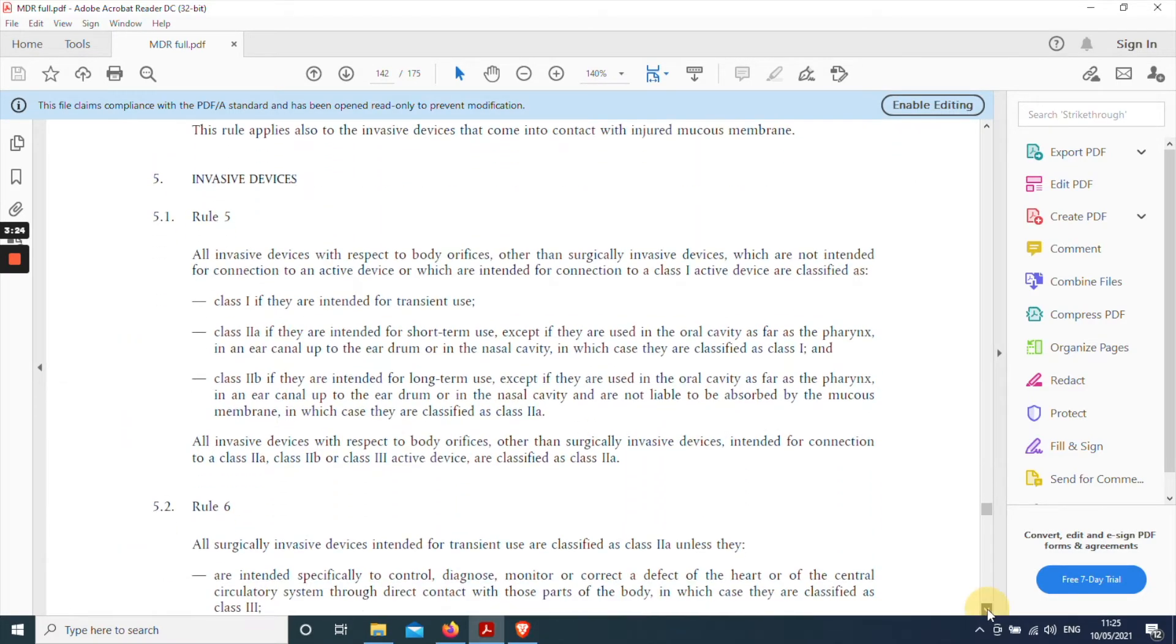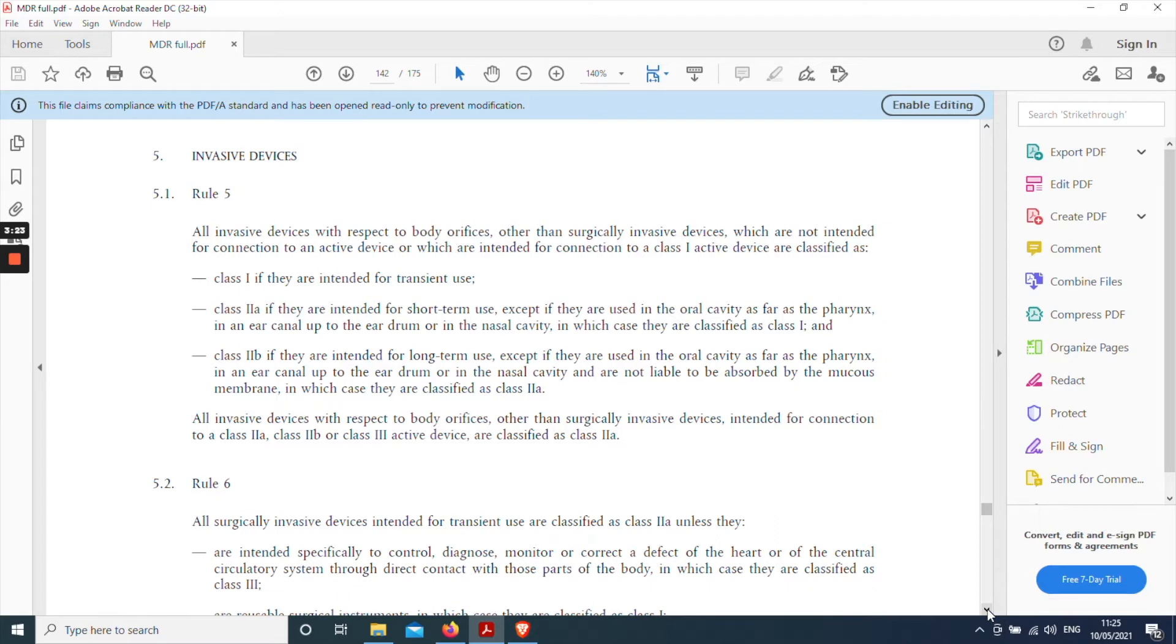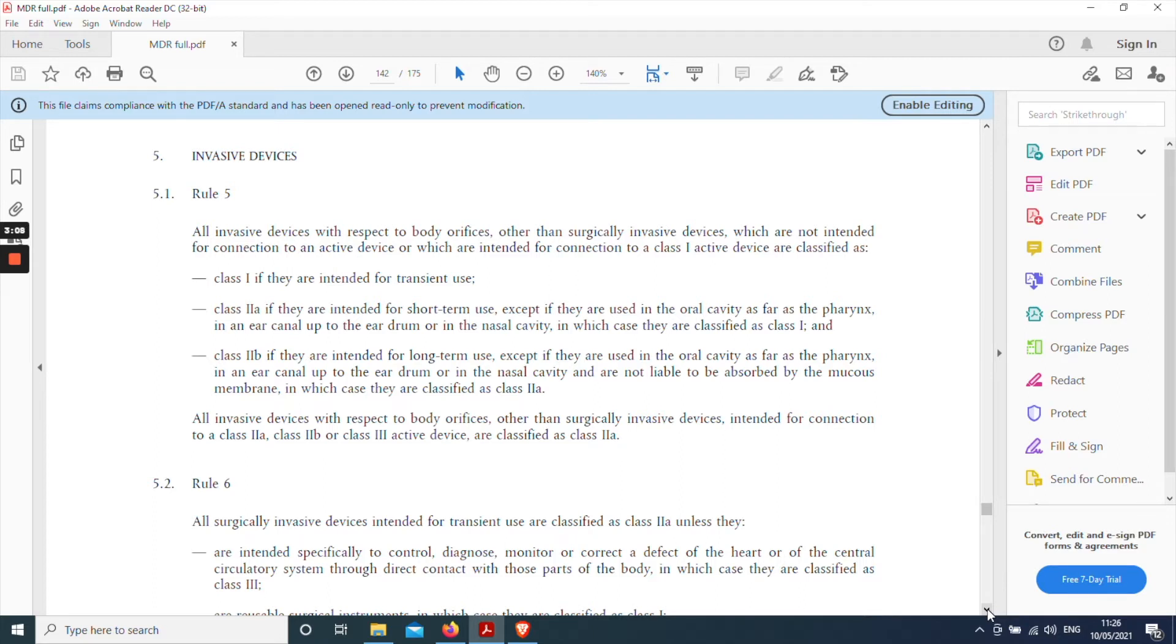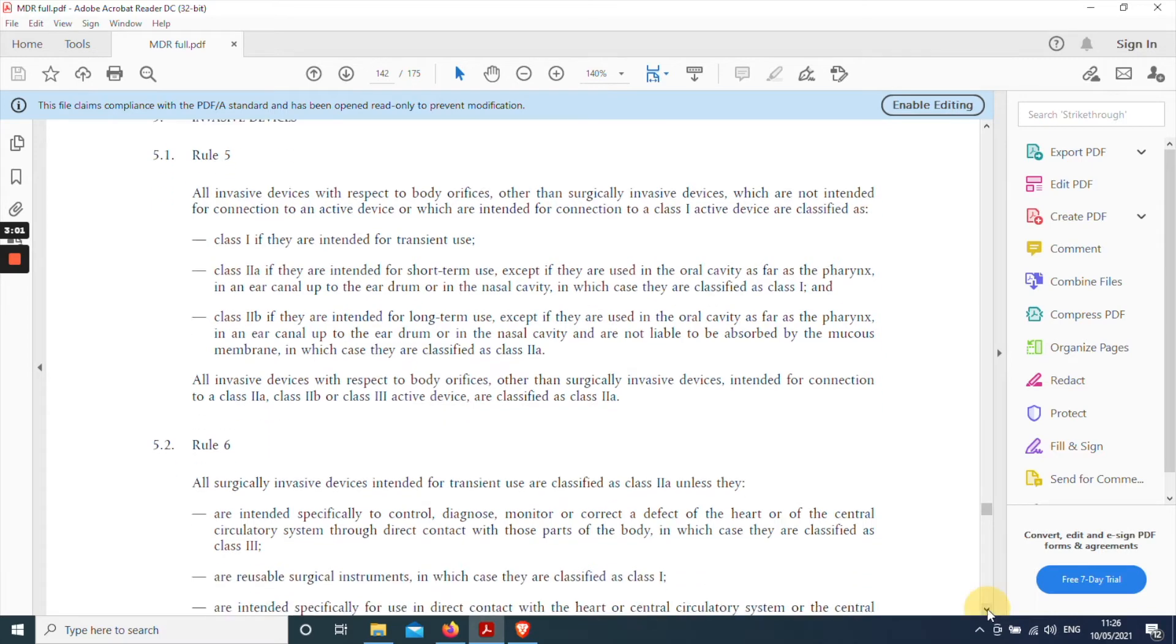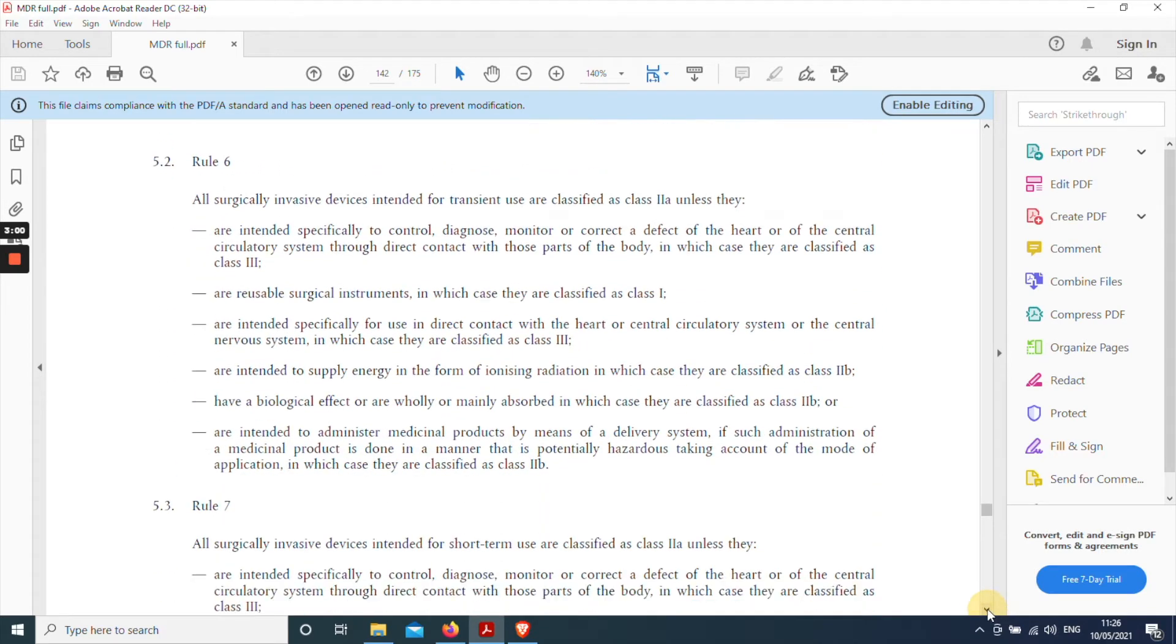And then we move to part five which is about invasive devices. So we're in the right section now. So we need to look in detail the rules in this section. Rule five states or begins with a stem sentence all invasive devices with respect to body orifices other than surgically invasive devices. So we can stop reading there because a cardiac pacemaker is a surgically invasive device. We can move on to rule six.